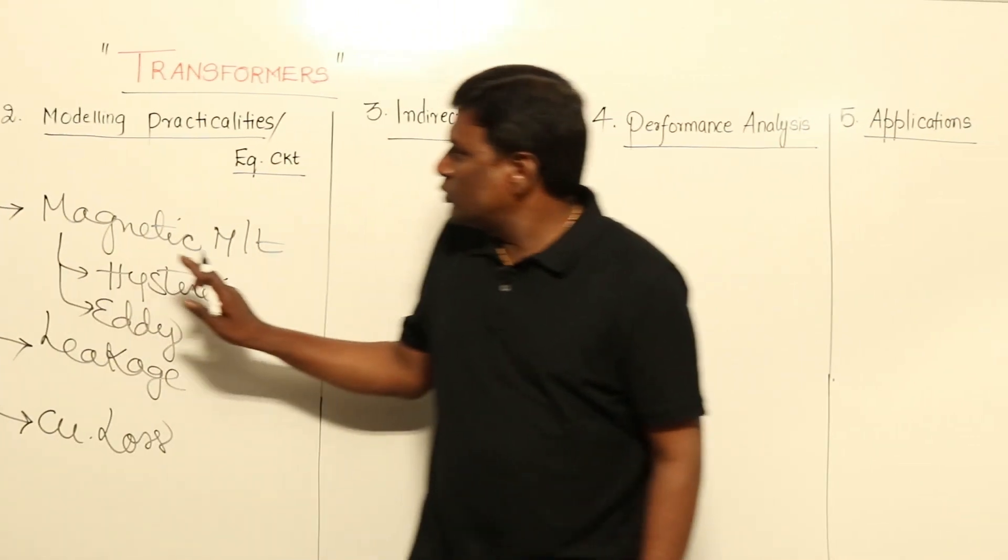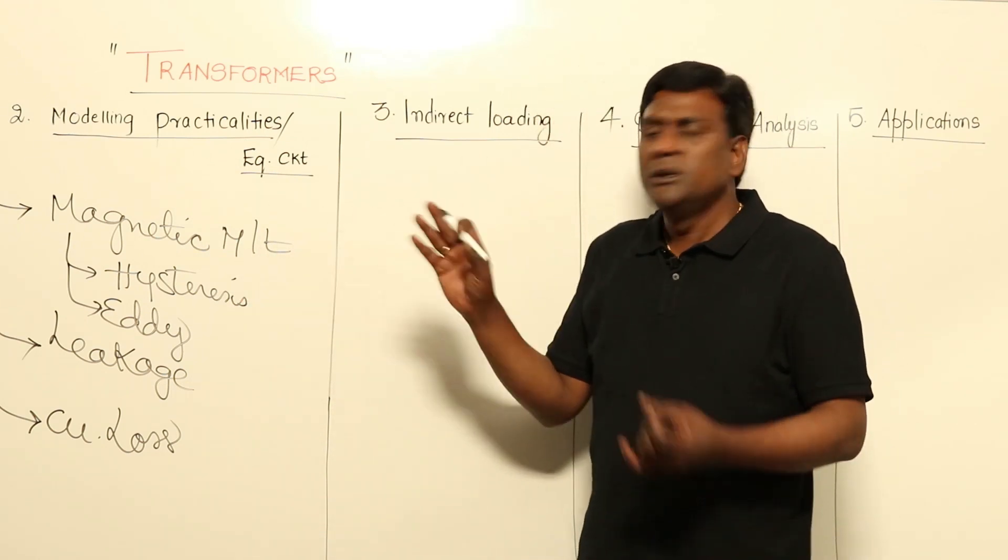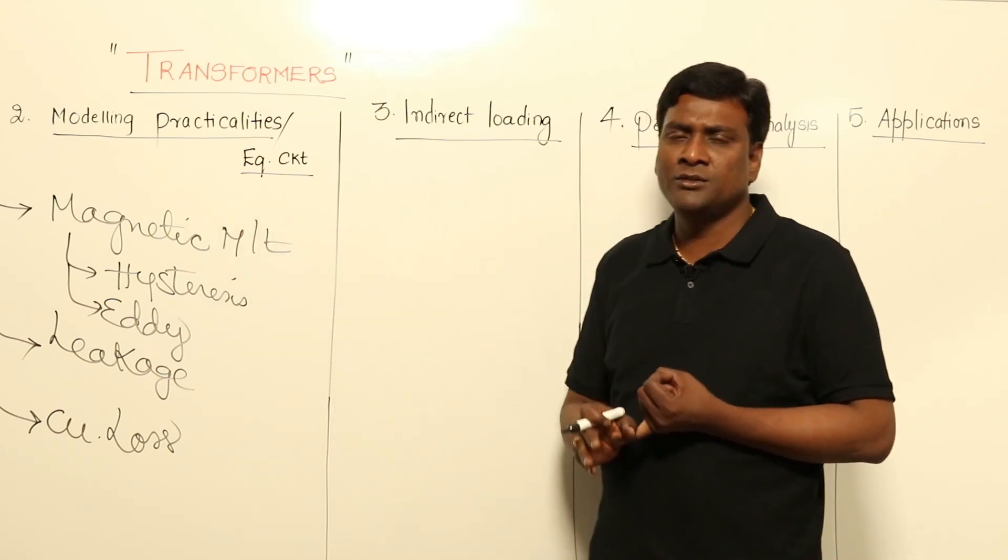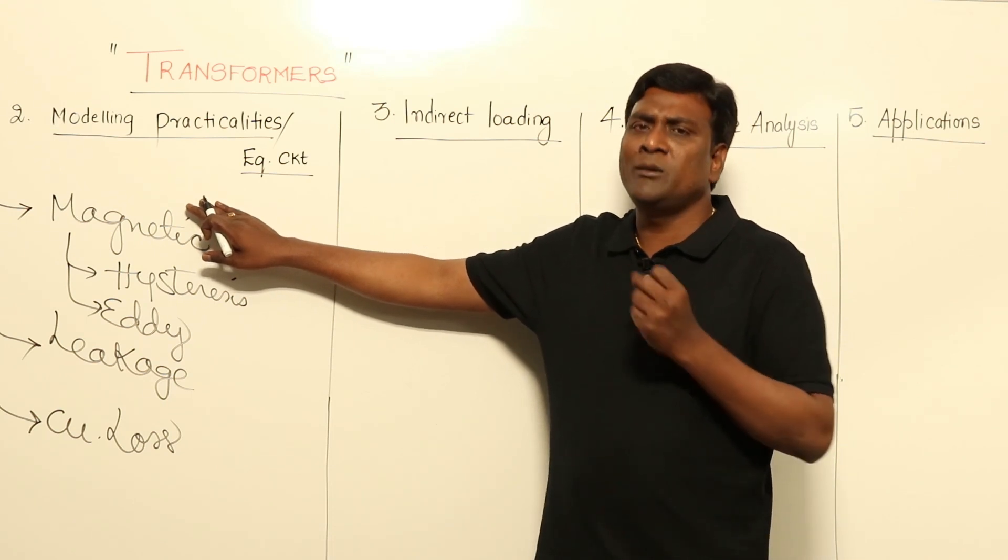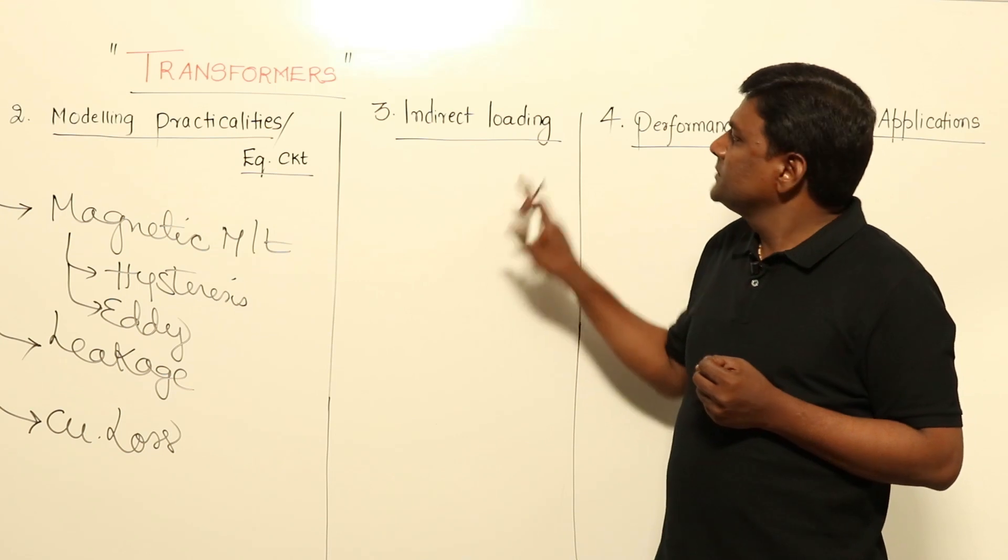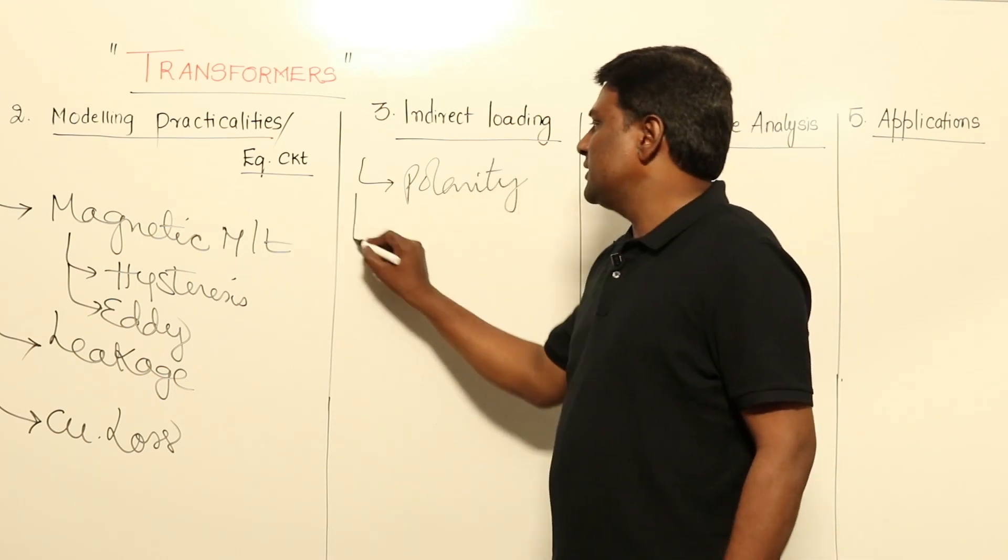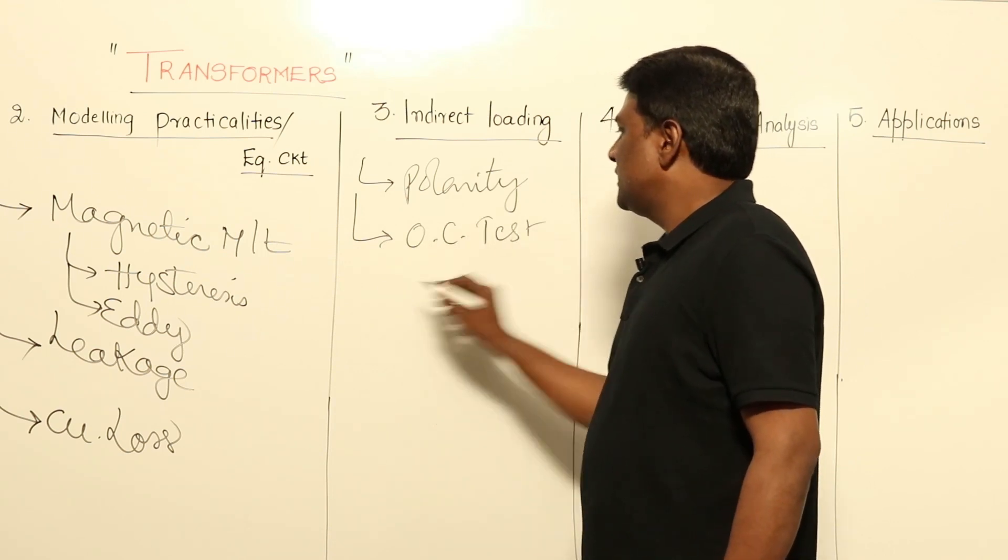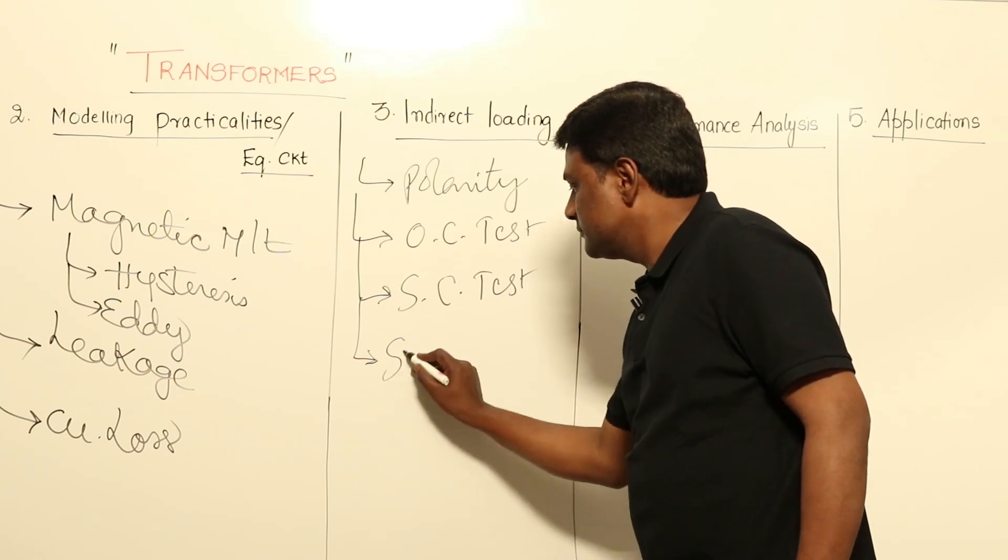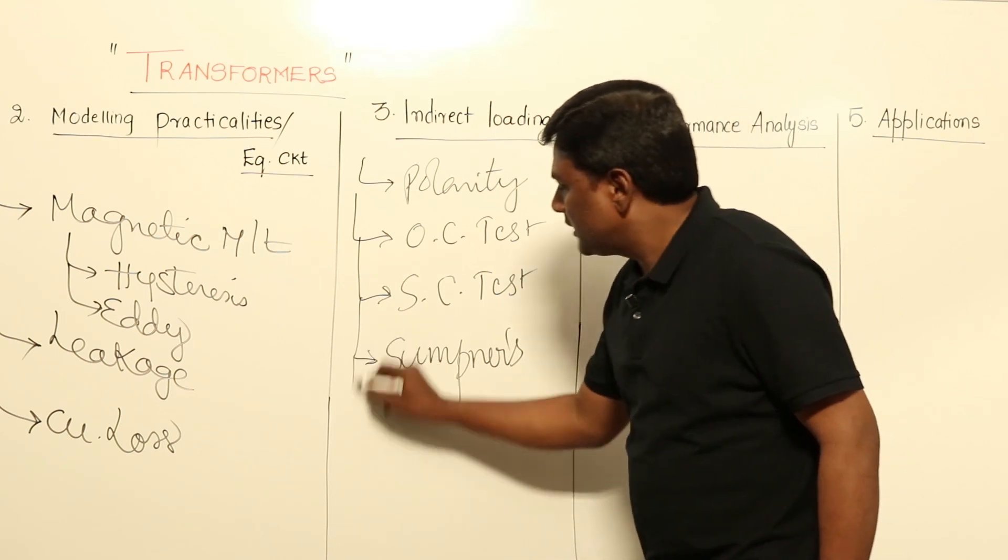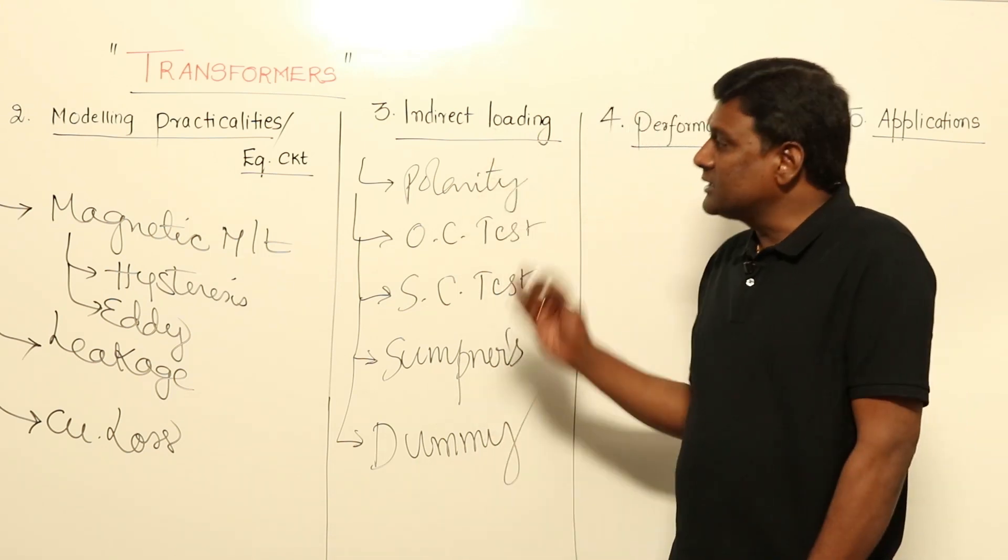Now phase three is going to be here. You are going to find out by which parameters those practicalities has to be modeled. In phase three, we have to find those parameter values of equivalent circuit. For example, if I consider in phase two a resistance, how much is the value of resistance will come here. Leakage will be modeled in the name of inductance. How much is the value of inductance has to be understood here. Now in indirect loading, how many tests will be there: polarity test will be there first, after that OC test will be there, after that SC test will be there, and after that Sumpner's test will be there, and after that dummy load test will be there. These are going to be tests we are going to conduct in order to find parameter values.